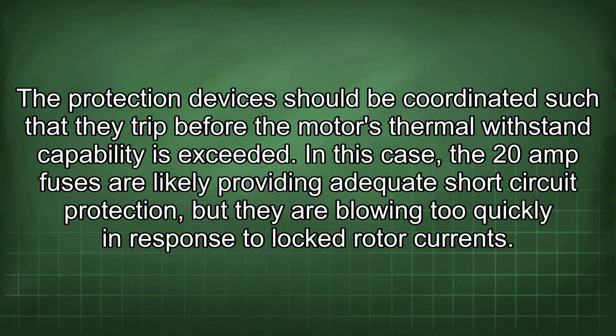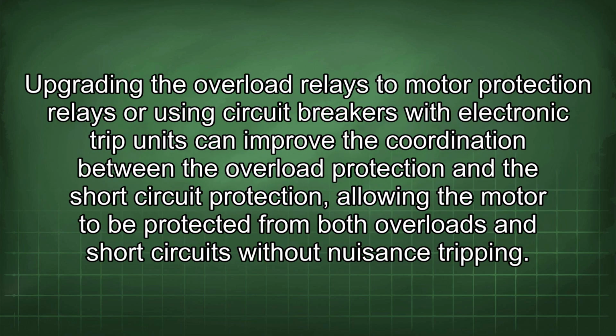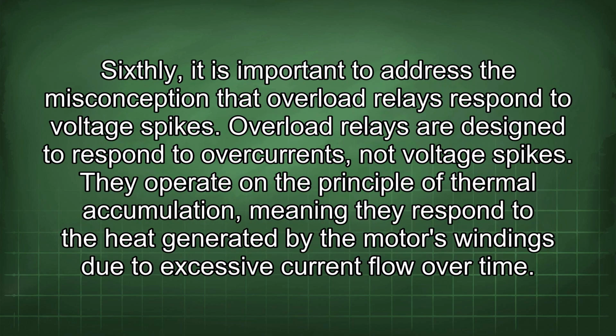In this case, the 20 amp fuses are likely providing adequate short-circuit protection, but they are blowing too quickly in response to locked rotor currents. Upgrading the overload relays to motor protection relays or using circuit breakers with electronic trip units can improve the coordination between the overload protection and the short circuit protection, allowing the motor to be protected from both overloads and short circuits without nuisance tripping. Sixthly, it is important to address the misconception that overload relays respond to voltage spikes.